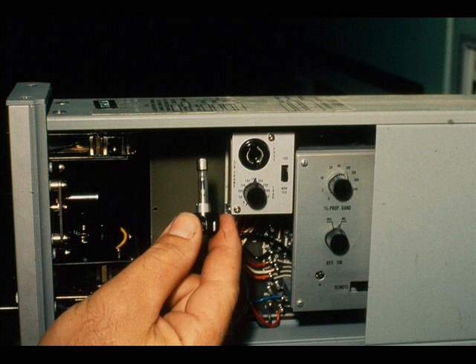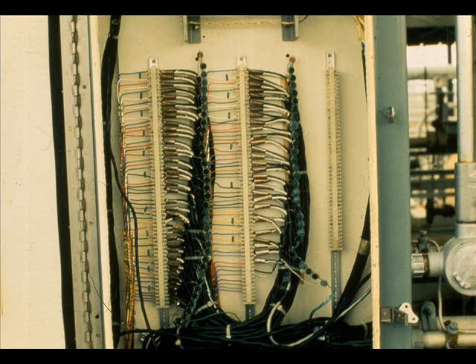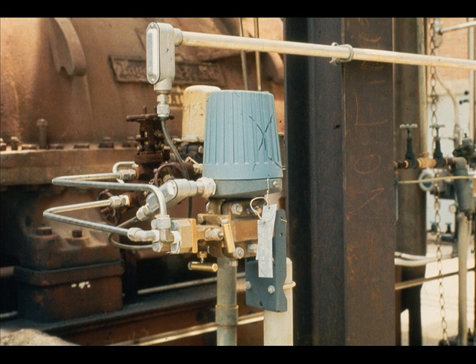If there is zero voltage at the terminal strip, it is a good indication that a fuse is blown. If the DC voltage is normal at the control center terminals, our trouble will be in the signal wires to the transmitter or the transmitter itself.